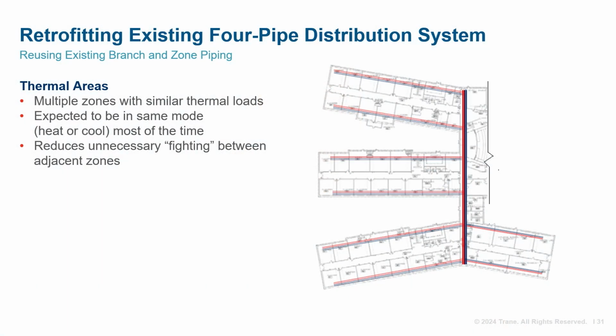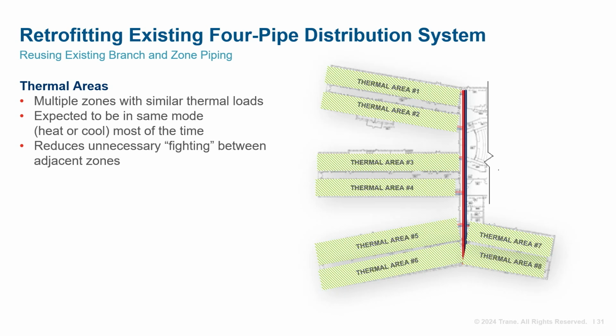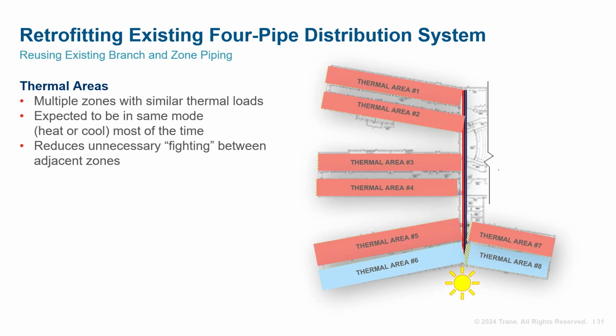In the shoulder months, there may be early morning or late afternoon solar loads that require cooling in some of the areas, while heating is needed in others. This can be true if there's a dedicated outdoor air system serving fan coil units that do not economize. In our example school building, the classroom wings can be divided into 8 thermal areas. Throughout most of the year, these thermal areas will require either cooling or heating, but for those few early morning fall or spring sunny days, some of these thermal areas require cooling, while the rest need heating.